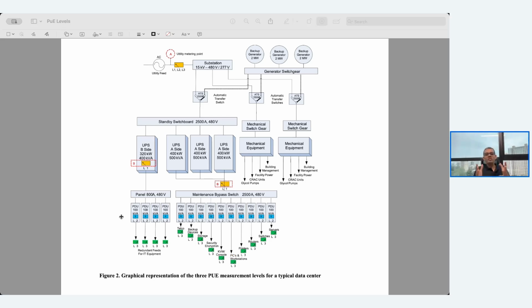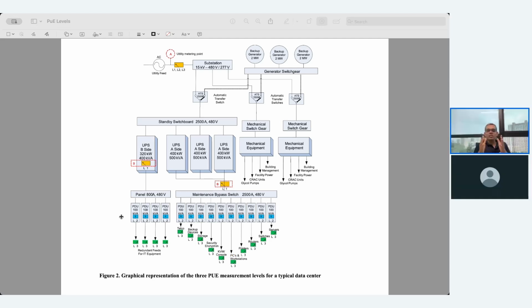The next and the advanced one, which is at the IT equipment level, ideally speaking, you should have a continuous measurement at least at every 15-minute interval. That gives you a good enough idea about an annualized PUE figure. That is what you're more interested in. Again, PUE is best compared on an annual basis, and that's how it's supposed to be. On an annual basis, how is your PUE, what is it, and that's what you are going to be focusing on. So that's a very basic primer with respect to PUE.